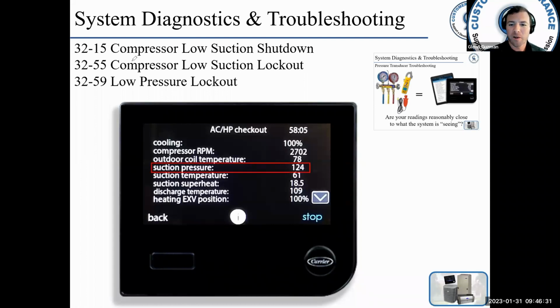We added 3259 here. So let's see, 3259 is triggered when the suction pressure is too low to safely start the compressor. All right, so refrigerant saturation pressure is low enough, the system will be inoperable until pressure increases to an acceptable range. What could cause that? No pressure in the system. You know, maybe there's a large leak, and it leaked all the refrigerant out. There you go, 3259.